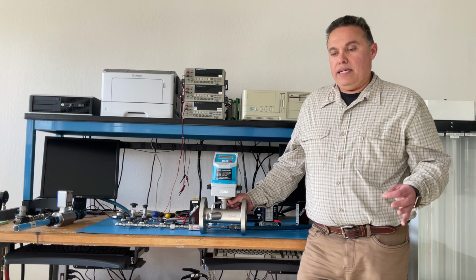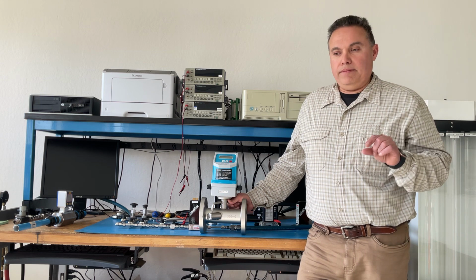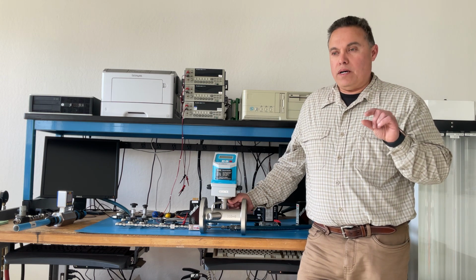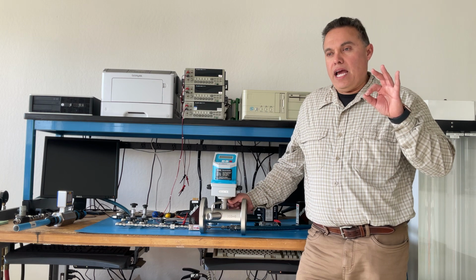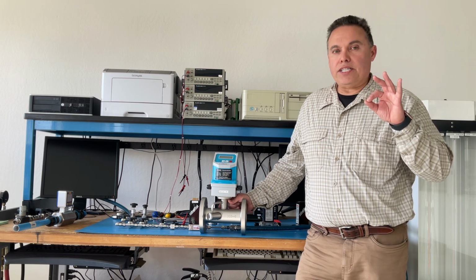We don't just stop there. We go the extra step, and what we do is we find where there's deviation between our data points and compare it against the reference standard, and any kind of deviation, whether it be very small or all the way up to 0.5% or 1%, we'll literally take that data point, and we'll use a trim function, and that trim function effectively corrects any kind of deviation so that it's perfect. You don't get any error in between the device under test and the reference standard.